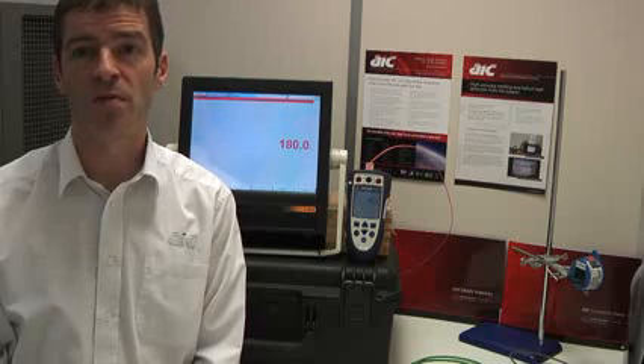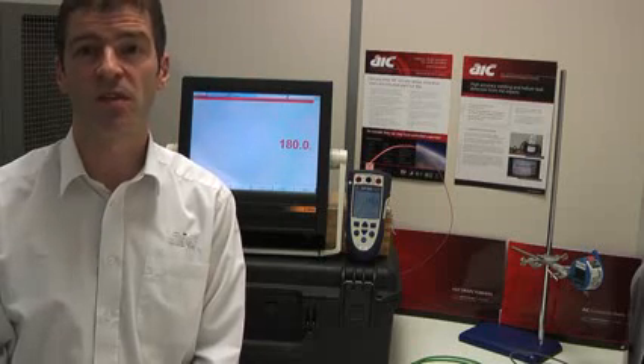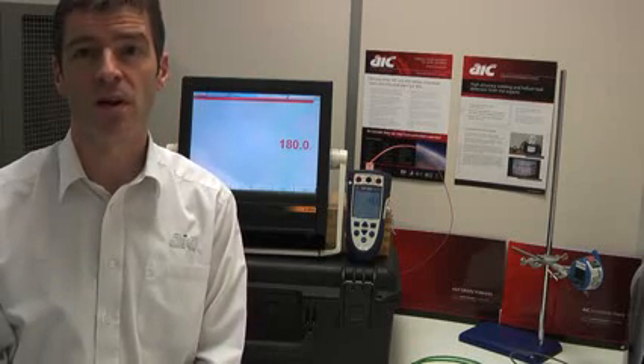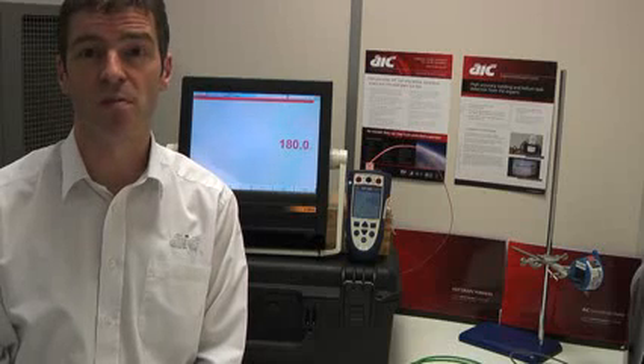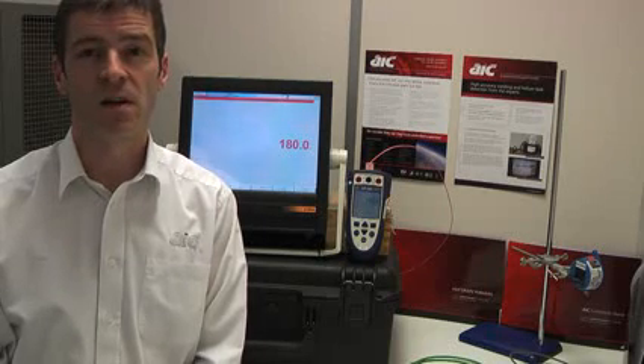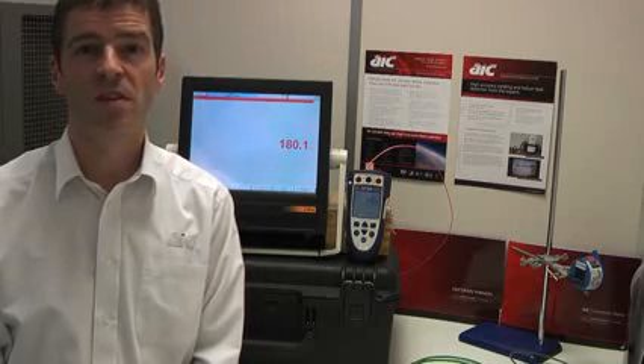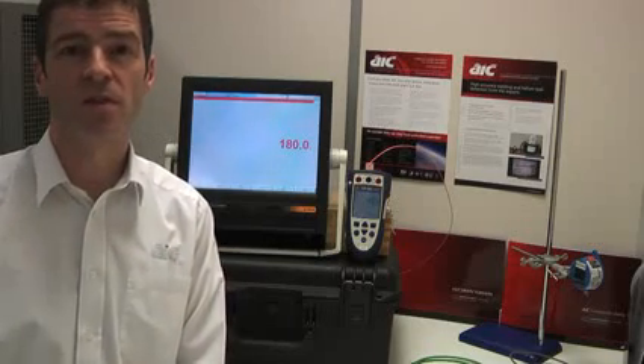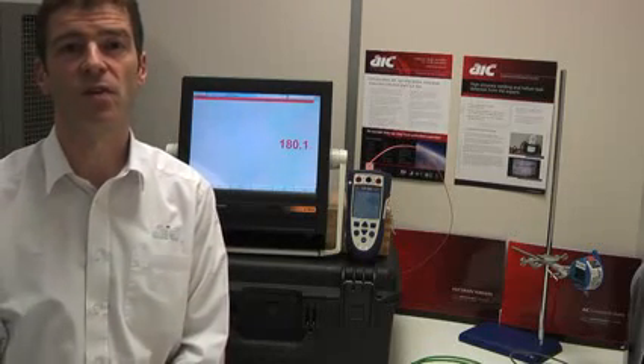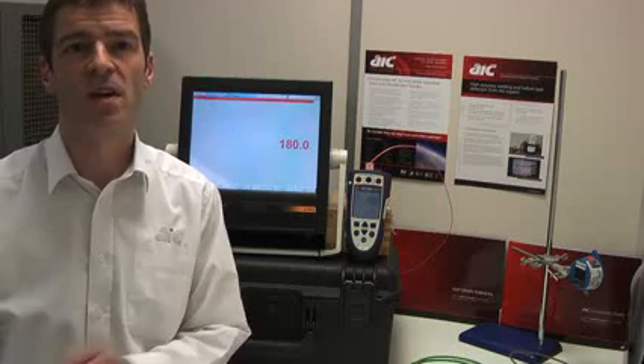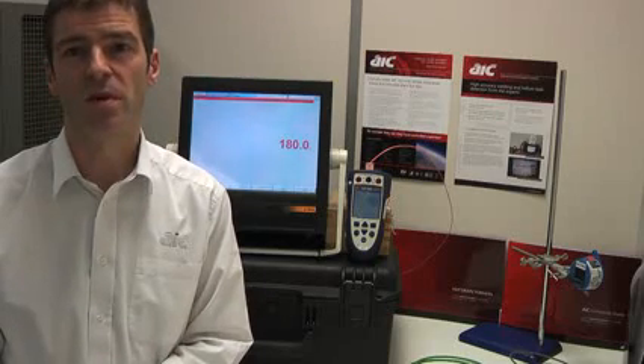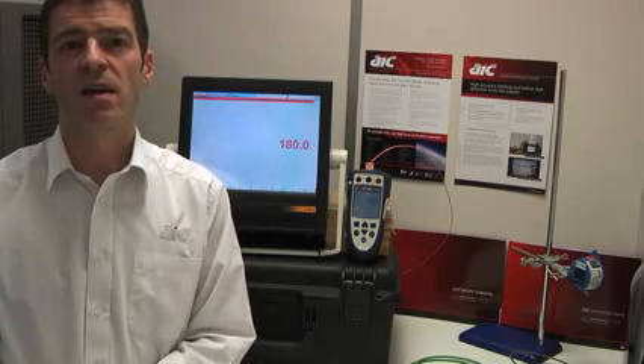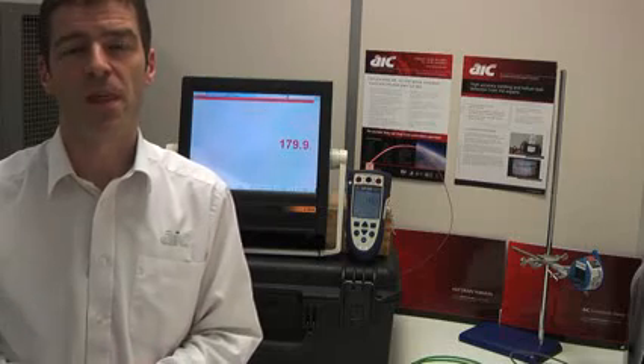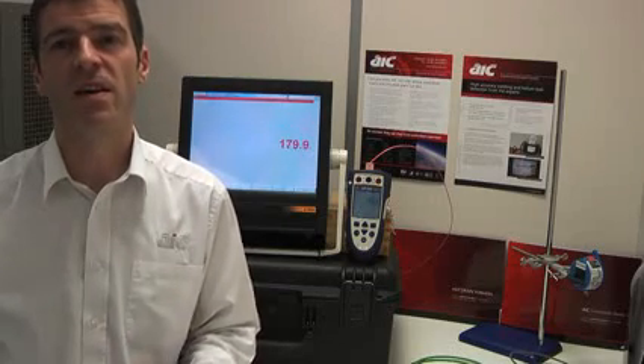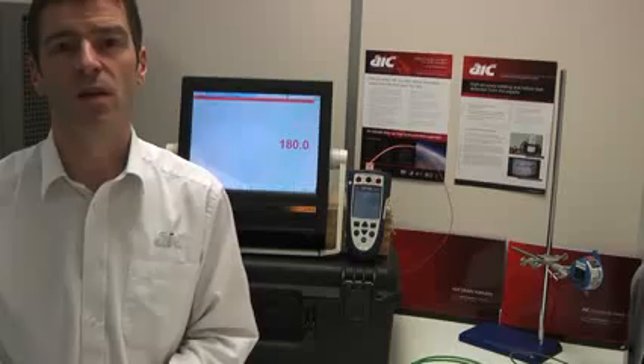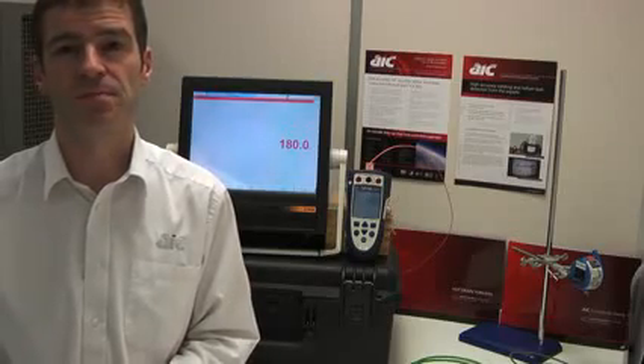I'll talk briefly about some misunderstandings about how thermocouples work and how this can introduce errors into measurements. This time it's been suggested that calibrating an autoclave or oven by simulation from the internal sockets provides some assurance that the permanently installed part of the thermocouple cable is not a source of error. Now, if this was correct, then any defect in that thermocouple cable would be detected during the calibration.